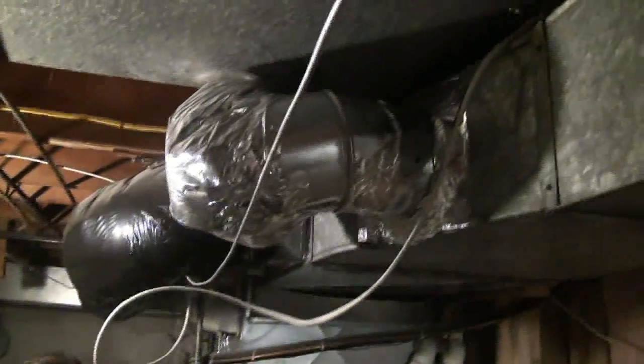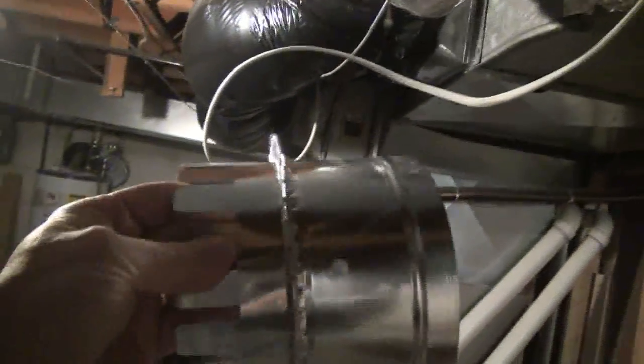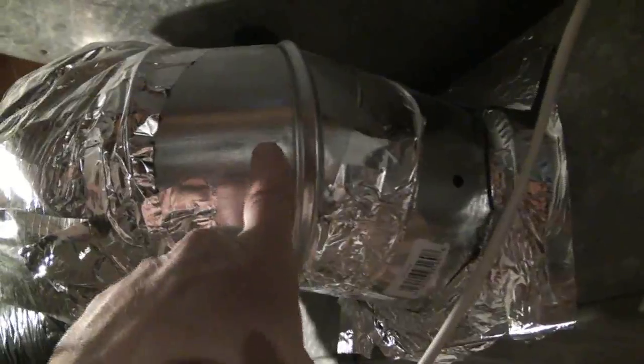We also use these for the return air. And then we went right into a 90 to make our turn nice. Yeah, we came out with the 6-inch boot. We turned it into a 90, which we connected onto the boot, and that brought us around in a nice 90-degree motion here, so we didn't pinch off our flex duct. And then we went up and over into the floor joist cavity right there, and then that shoots straight over into that other bedroom where we're coming down through the ceiling.